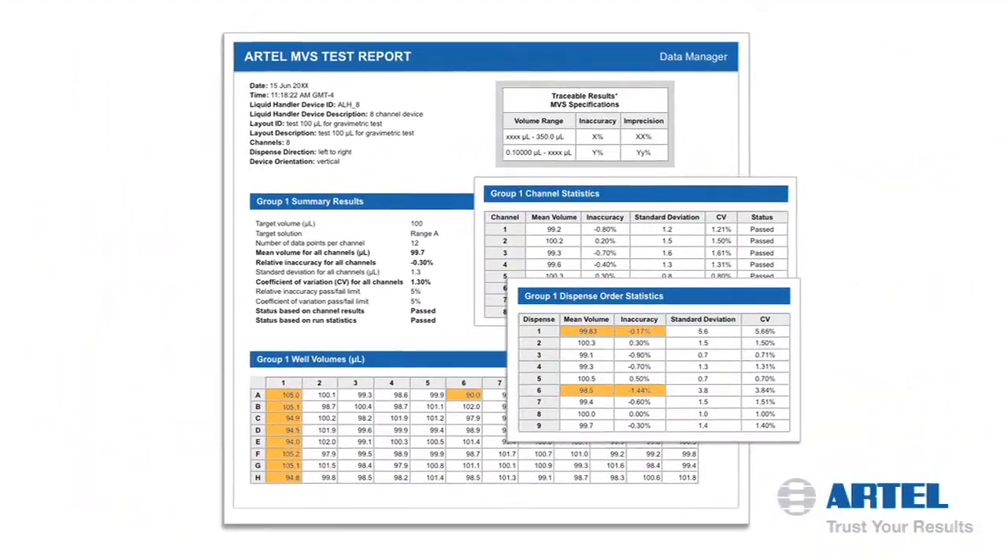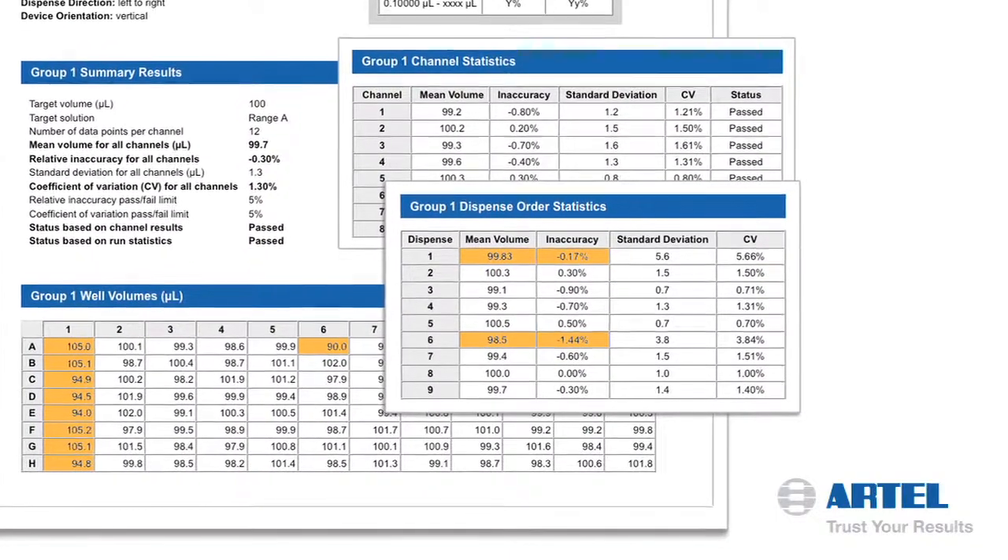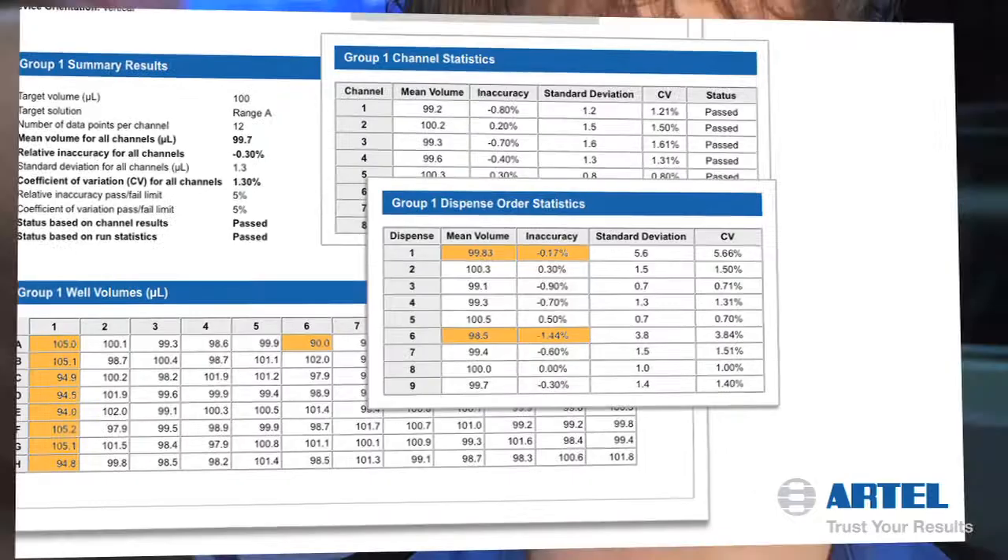We use a ratiometric calculation using the absorbances of those two dyes to calculate the volume in every well. It results in a precision and accuracy measurement for every well of a plate in just minutes, versus other methods which can take sometimes days or hours to complete. With the Artel MVS we allow people to measure the volume dispensed by their liquid handlers down to 10 nanoliters and in some cases up to one milliliter.